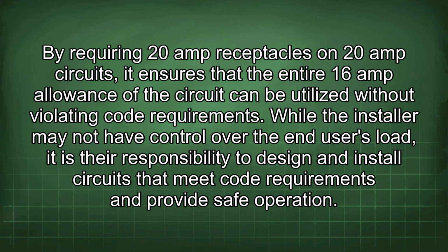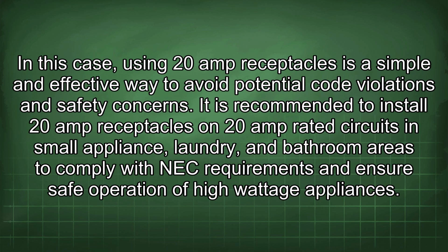without violating code requirements. While the installer may not have control over the end user's load, it is their responsibility to design and install circuits that meet code requirements and provide safe operation. In this case, using 20-amp receptacles is a simple and effective way to avoid potential code violations and safety concerns. It is recommended to install 20-amp receptacles on 20-amp rated circuits in small appliance, laundry, and bathroom areas to comply with NEC requirements and ensure safe operation of high-wattage appliances.